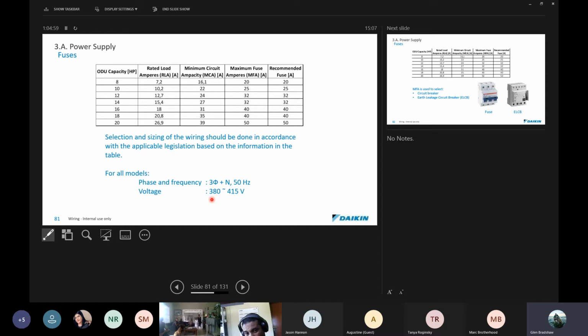When it comes through to the commissioning stage, I'll also just mention to you guys, that'll be in the next section of work that we look at, that does not mean that you're going to have one phase at 380 and another phase at 415. These are the nominal voltages. The average is only allowed to be 3% either side of that.